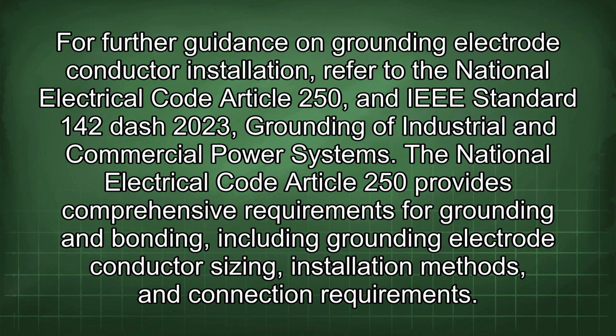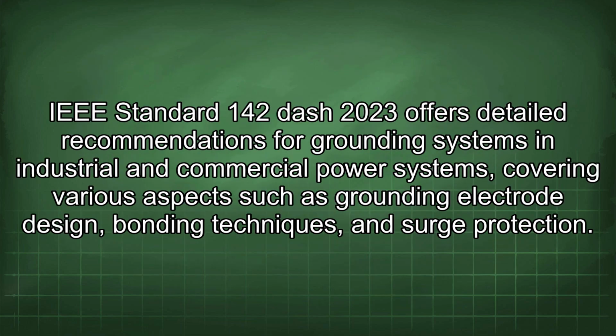For further guidance on grounding electrode conductor installation, refer to the National Electrical Code Article 250 and IEEE Standard 142-2023, Grounding of Industrial and Commercial Power Systems. The National Electrical Code Article 250 provides comprehensive requirements for grounding and bonding, including grounding electrode conductor sizing, installation methods, and connection requirements. IEEE Standard 142-2023 offers detailed recommendations for grounding systems in industrial and commercial power systems, covering various aspects such as grounding electrode design, bonding techniques, and surge protection.